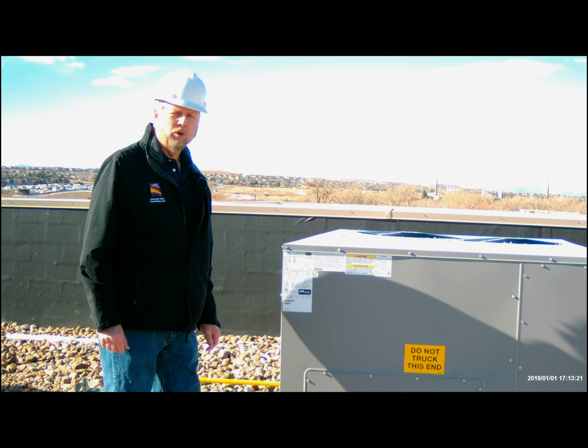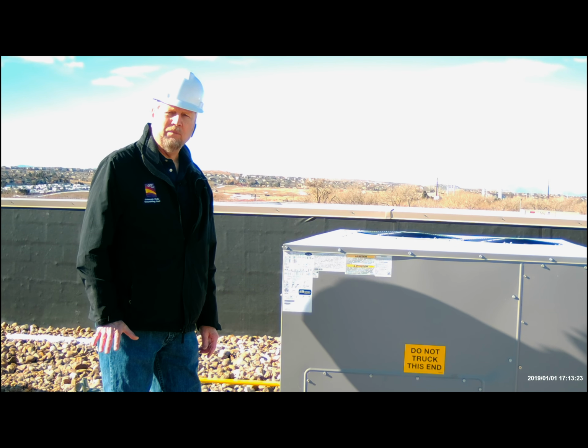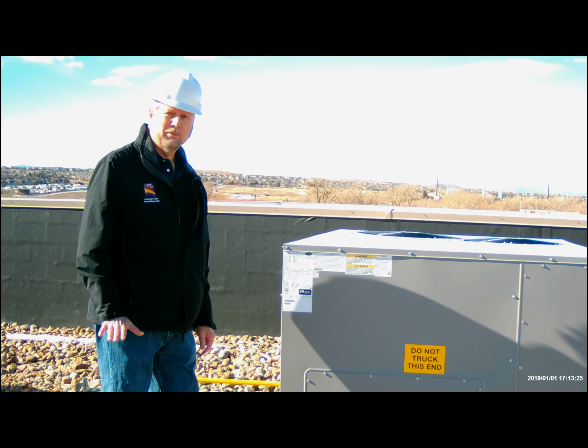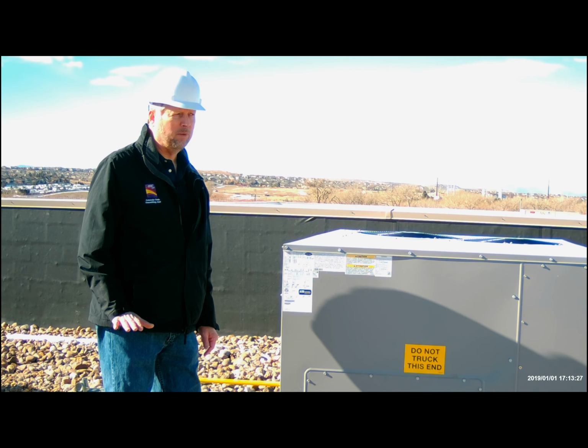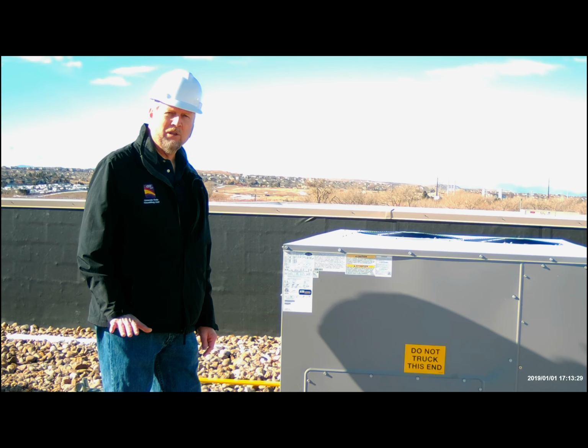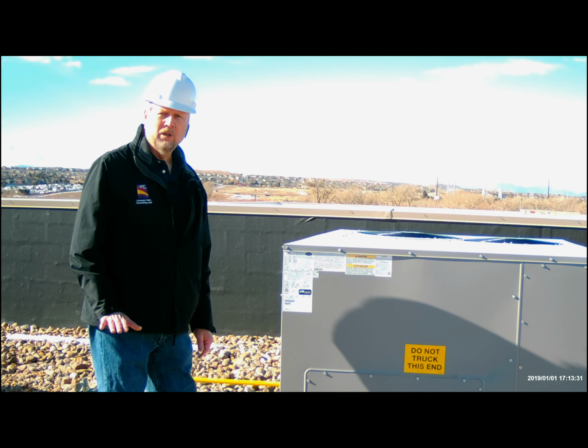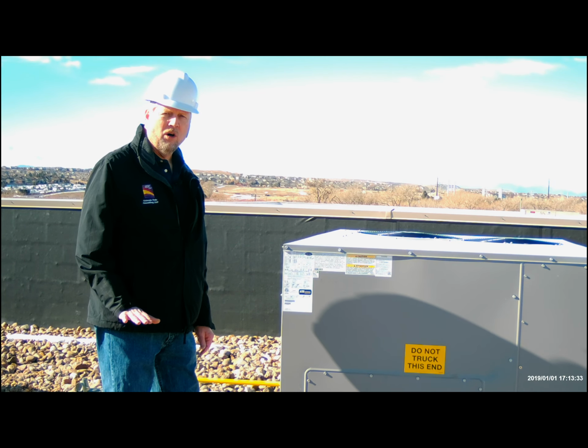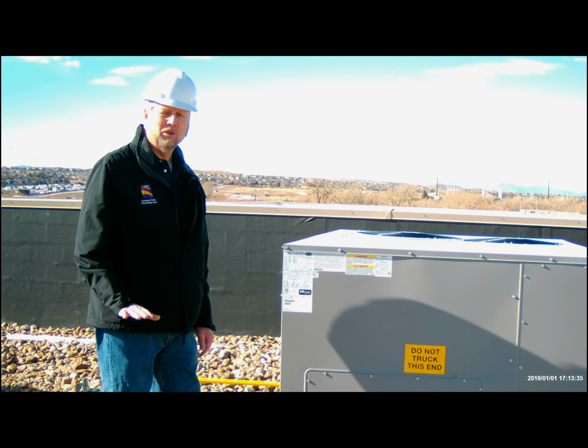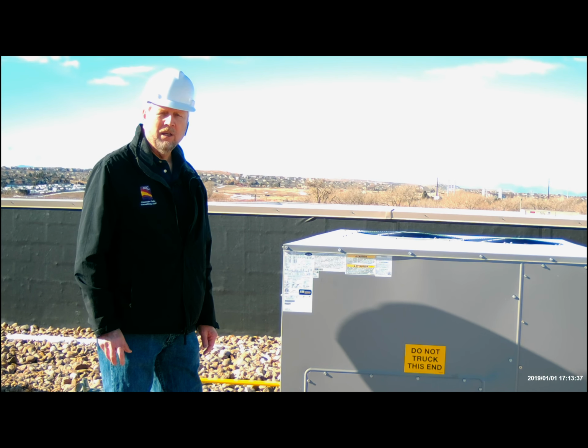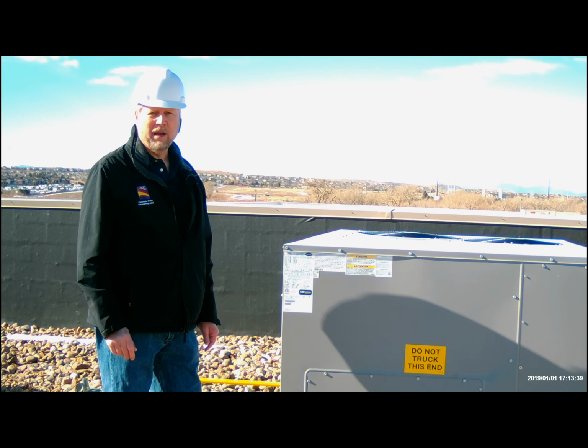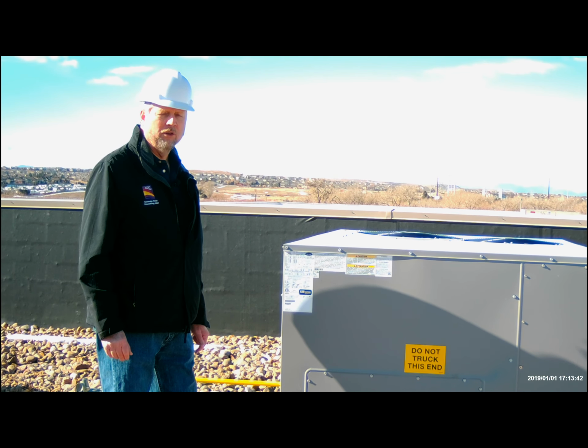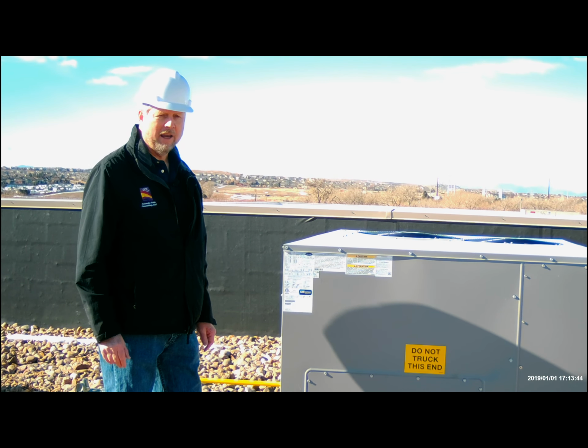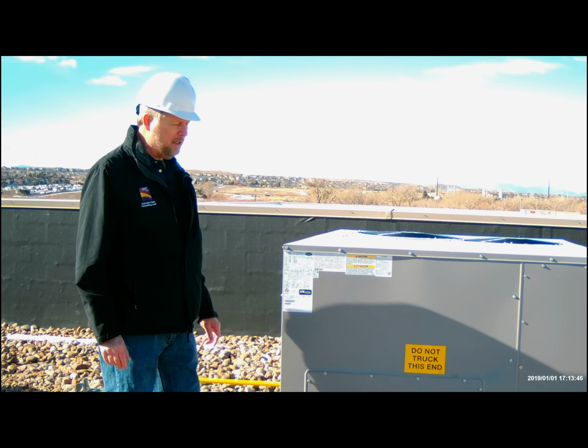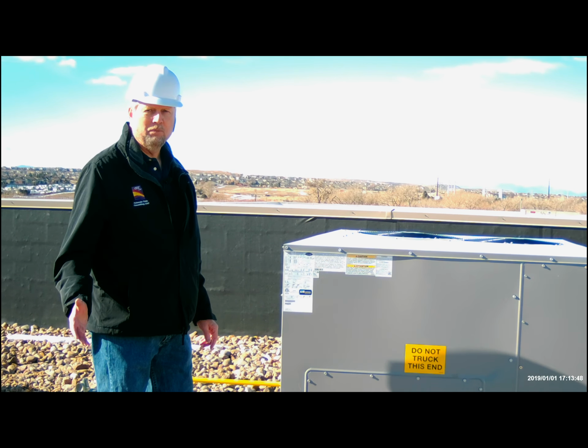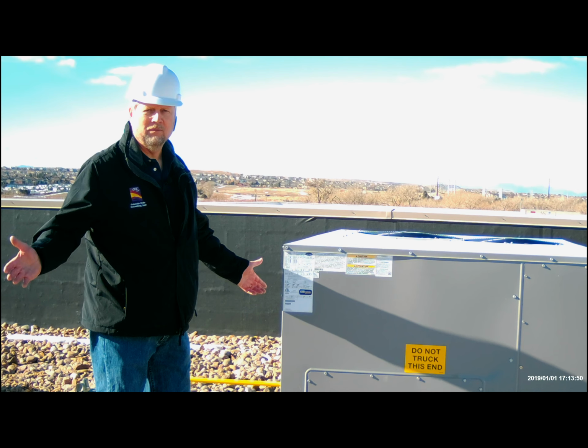So here we're on a rooftop of an actual existing commercial building where they've replaced pretty much all of the rooftop units. For the energy code, we need to make certain all the new rooftop units meet all the energy code requirements. Hopefully during our plan review process we got all the new equipment that's going to be supplied. Now when we're here on inspection, we're actually trying to verify: did they put what they said they were going to put, what we got through our plan review.